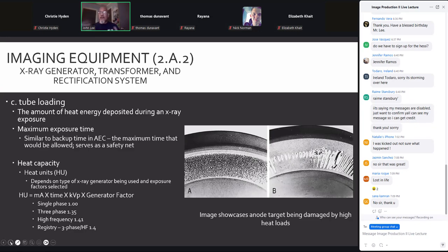Our maximum exposure time is going to be variable based on the manufacturer and its specifics. This is kind of like the backup time, but it's the maximum time that's going to be allowed. This serves as a safety net to protect the tube, specifically the anode, to keep it from cracking, melting, or pitting, which is this in B. This is a high exposure, but the bearings in the rotor are also bad, causing the rotor to stutter. It doesn't spin smoothly. So consequently, there are areas in which the electrons striking the anode have actually caused the anode to melt. This causes a problem with tube output because it actually enhances the anode heel effect by absorbing more X-rays that are being produced down within these dips in the surface of the anode.